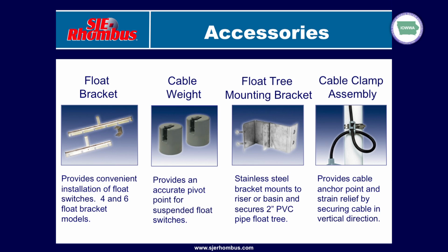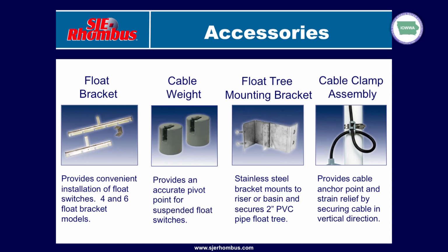There are other style cable weights out there that are available, whether it's two halves, like a clamshell lead weight design. There's a float bracket, so if you wanted to mount a float tree down into the tank, you could use something like that, or we can use cable clamp assemblies like what you see there. Those cable clamp assemblies can either attach to a float tree or the discharge pipe of the pump. Anytime you penetrate, whether it's a high level alarm, yes sir?